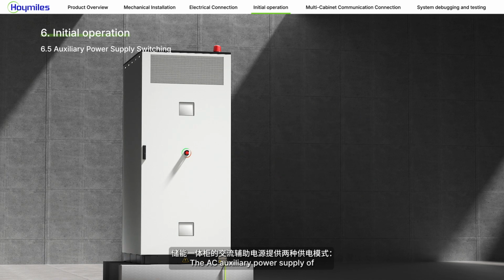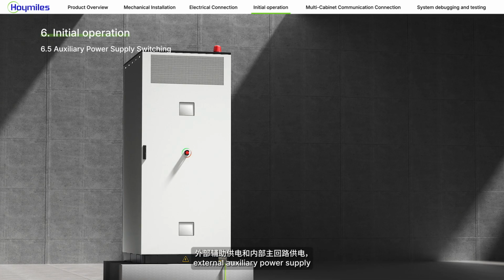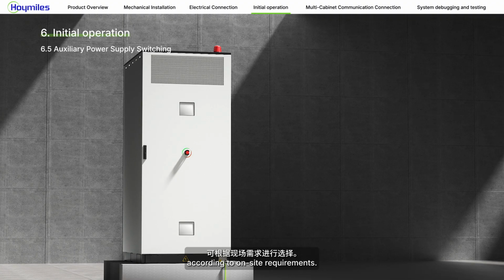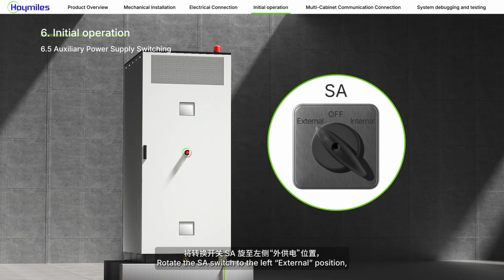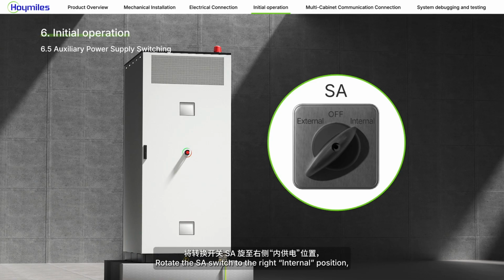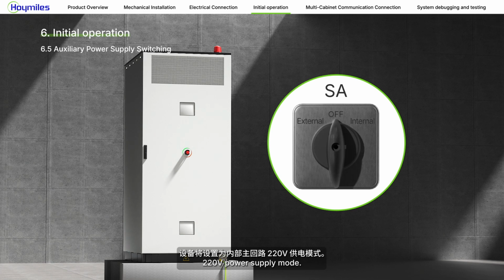The AC auxiliary power supply of the energy storage system provides 2 power supply modes: external auxiliary power supply and internal main circuit power supply, which can be selected according to on-site requirements. Rotate the SA switch to the left, external position, and the equipment will be set to external auxiliary 220 volts power supply mode. Rotate the SA switch to the right, internal position, and the equipment will be set to internal main circuit 220 volts power supply mode. Rotate the SA switch to the middle, off position, and the auxiliary circuit will be disconnected.